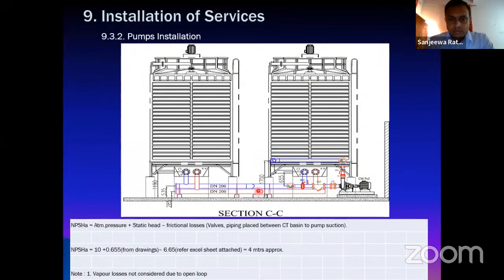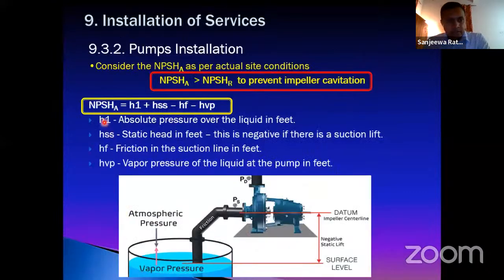Here is also one example of NPSH calculation. I just show here how it is calculated. Here I explain this H1 in NPSHA. The H1 is the atmospheric pressure, and HSS is the static head. Sometimes it may be a positive value, sometimes a negative value. In the picture here, the pump is above the water level, so the static head HSS is a negative value.